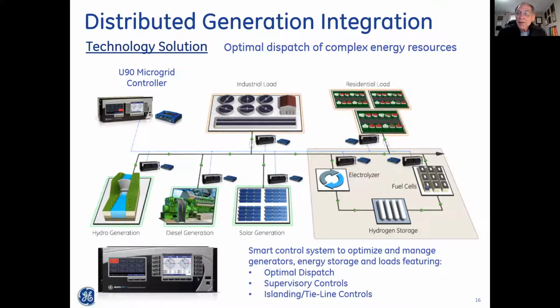So we took a microprocessor-based relay, the U90, shown in the upper left, and added logic to it to become the microgrid controller. Every 2 seconds it ensures the load is satisfied while minimizing use of the diesel generation and maximizing use of the hydrogen fuel cells, solar generation, and hydro generation. All the little blue boxes throughout are high-speed communication devices, so we know exactly what's happening throughout the whole microgrid every 2 seconds.